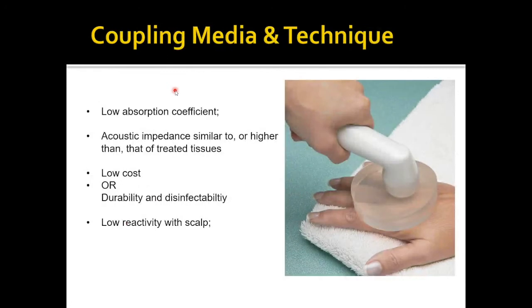I want to talk a little bit about coupling media and technique, because it's imperative, as we all know, to eliminate the air layer between the transducer and the subject's skin, because air reflects almost all of the ultrasonic energy, almost 100%. For the ultrasonic beam to reach the brain effectively, you want a material between your transducer and the scalp that has a low absorption coefficient and an acoustic impedance similar to or higher than that of your treated tissues. In this case, that's not the brain, it's the scalp, because that's what's in direct contact with your transducer.